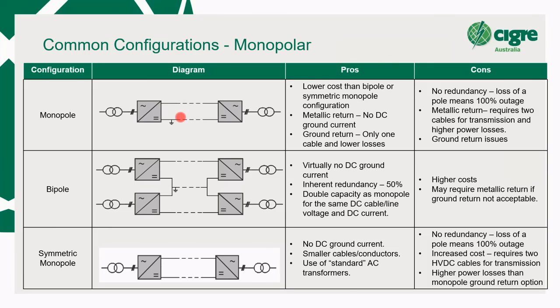So the metallic return cable or overhead line can be at a much lower voltage, like a medium voltage level. The benefit of a monopole is it's relatively cheap. You only need two cables instead of three compared to a bipole. The disadvantage is that if you lose the converter or you lose the cable, you've lost 100% of your link. So there's no redundancy in the system. And of course, if you try to put in a ground return instead and just get away with one cable, you may have issues with the ground return, such as electrode erosion, parallel buried metallic structures, the magnetic saturation of transformers, and then there are the environmental impacts that people talk about.